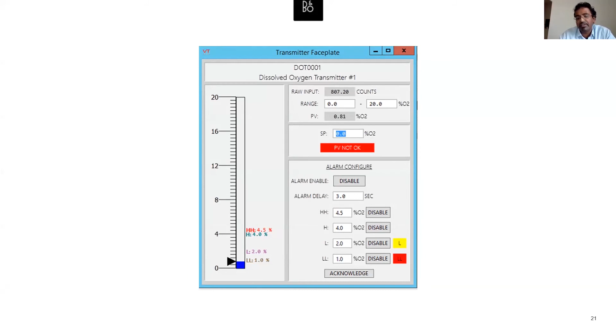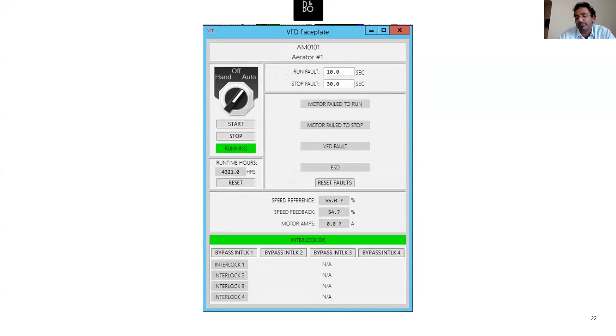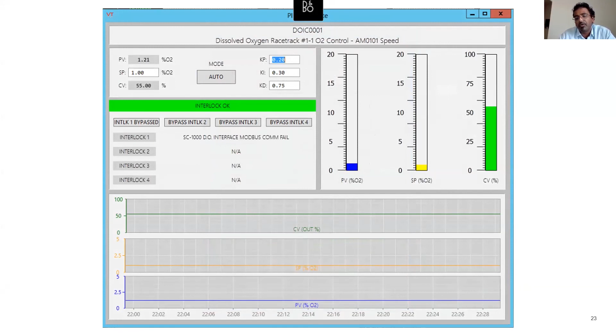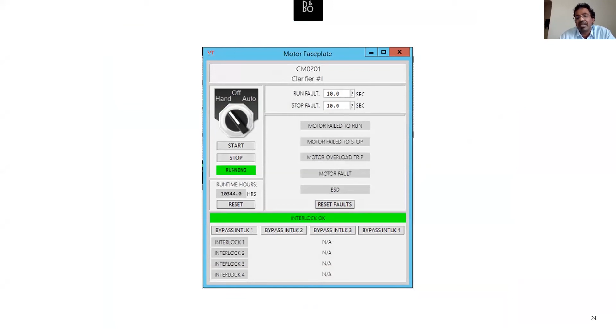Also, just to demonstrate, these are some custom graphic faceplates. This is a faceplate for a transmitter that we developed in VT SCADA and maintain as a local library. This is the faceplate we designed for controlling a VFD using VT SCADA's native elements and custom graphics. This is the PID control faceplate for the aerator motors at the wastewater treatment plant, and this one is a motor control faceplate for controlling standard on-off motor starters.